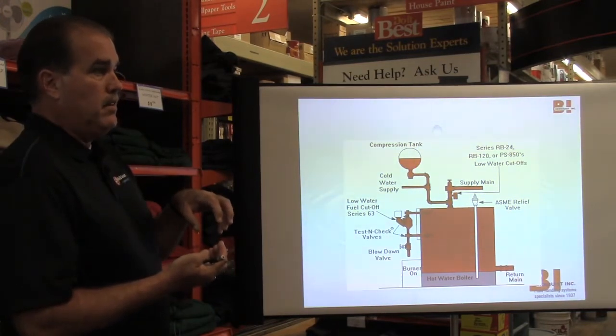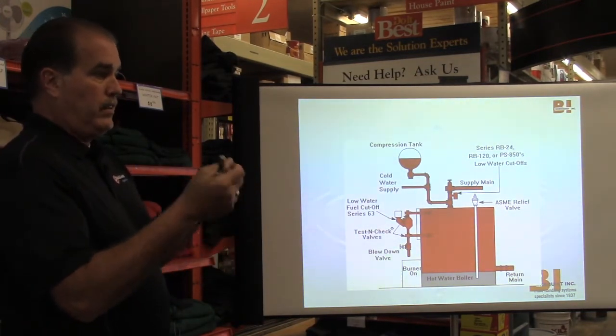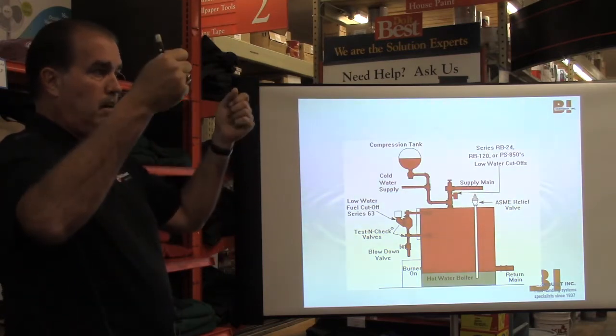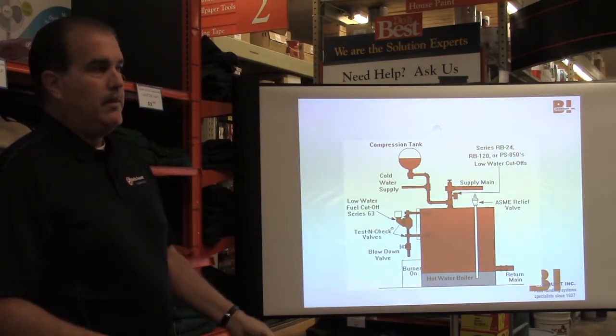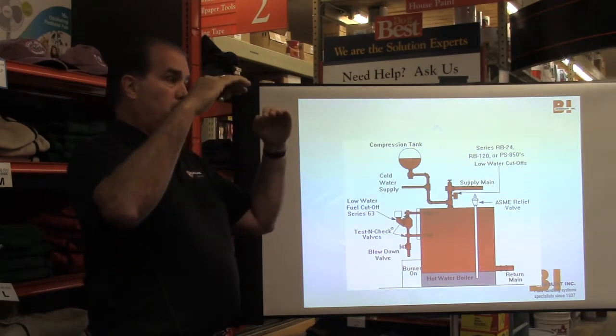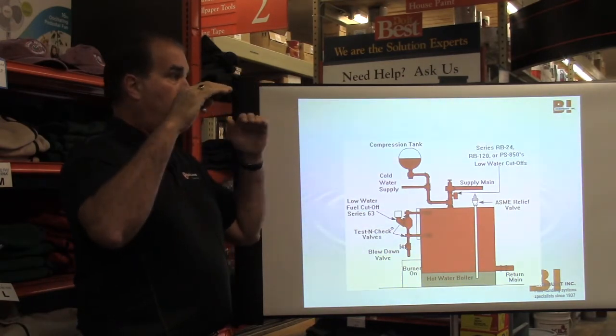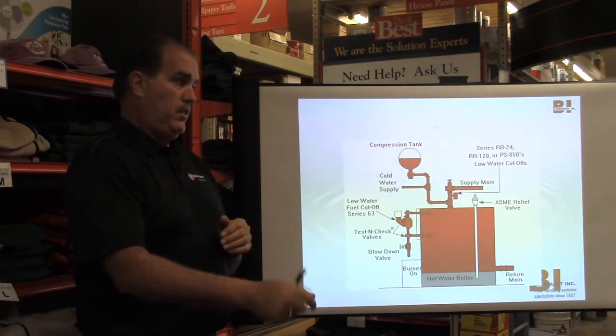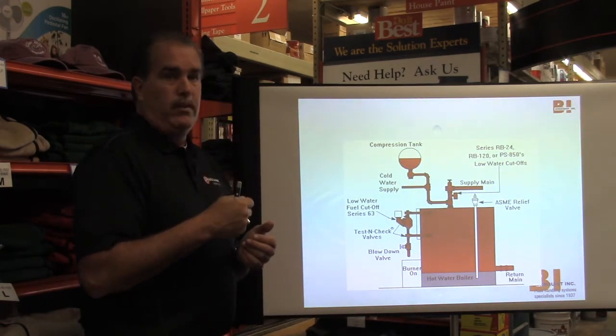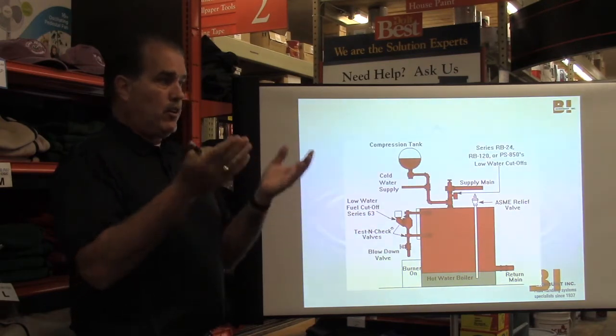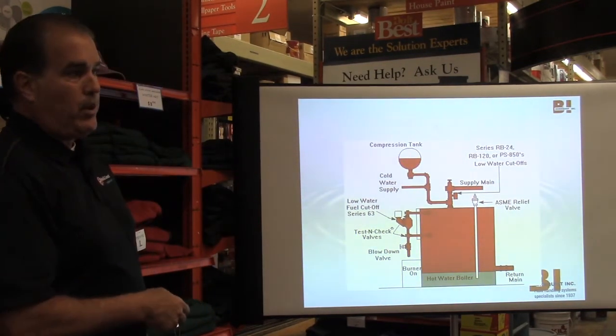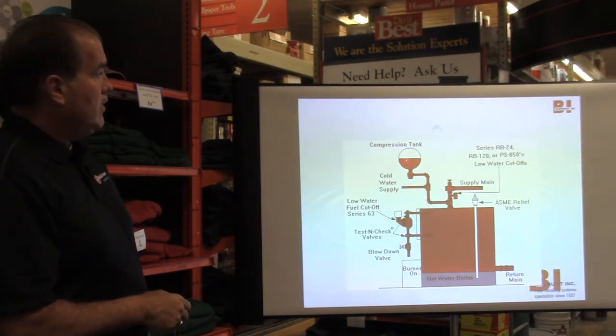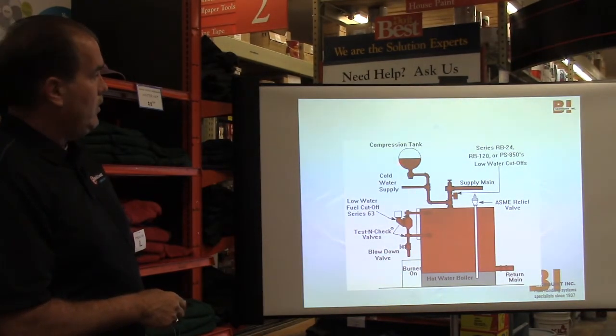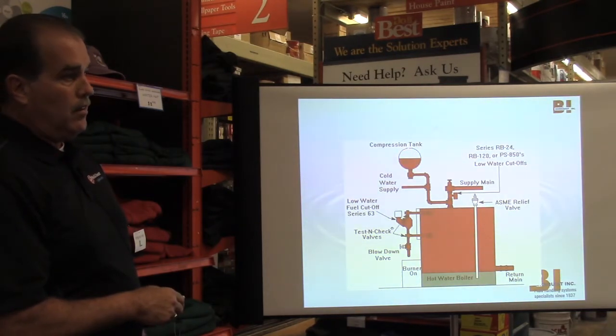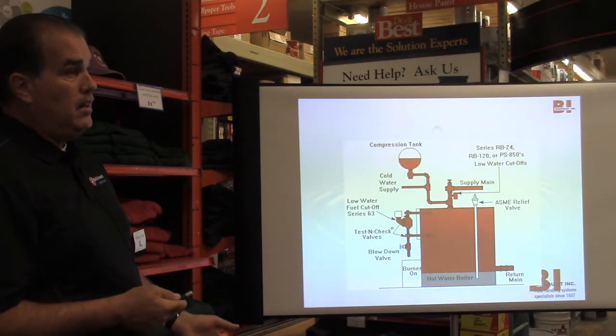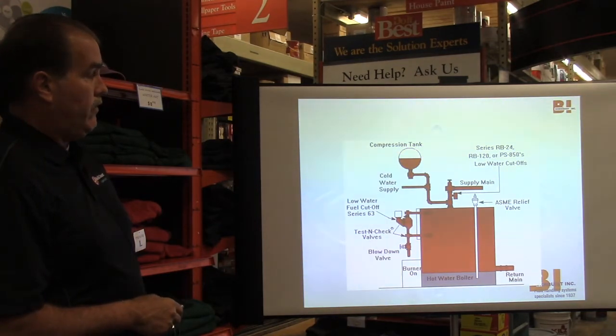Over time, it's not unlike in plumbing where they have the little water hammer arrestors. They don't go anywhere, they're just there to catch air, so that when you turn your faucet off, it doesn't go bam, bam, bam from water hammer. Those are cushions. The air cushions this fluctuation in pressure on the water side. However, over time, that air gets absorbed into the water, and the water slowly creeps its way up. It takes quite a while, but over a long period of time, it could eventually fill.